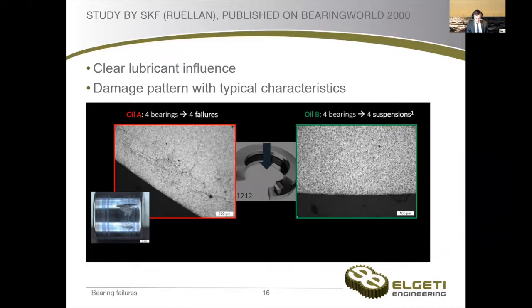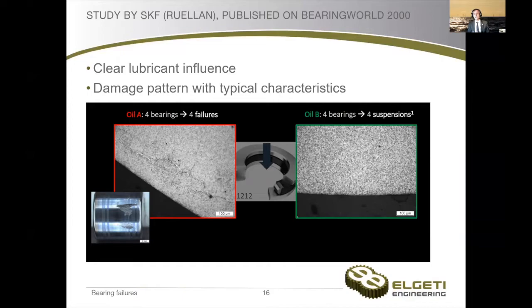Without jumping to conclusions, contamination might be an issue — but at least what we saw is that the oil in the condition as it was on the turbine was not good, was poisonous to the bearing, and therefore caused white etching cracks. And if we have an 18-year-old gearbox and nothing else changed, we can be pretty sure that the oil change was the root cause. While just from these observations, we will not be 100% sure whether it has something to do with the contamination or whether the oil itself was not okay from the very beginning — but this is something to be further analyzed and discussed.